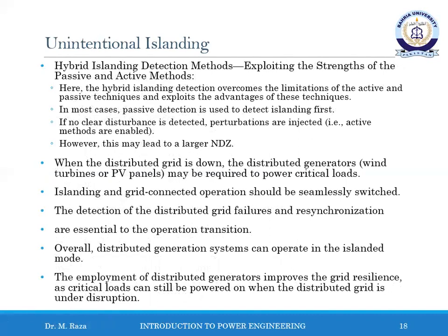Hybrid islanding detection methods use the strengths of the passive and active methods. Here, the hybrid islanding detection overcomes the limitations of the active and passive techniques and exploits the advantages of these techniques. In most cases, passive detection is used to detect islanding first. If no clear disturbance is detected, perturbations are injected, that is, active methods are enabled. However, this may lead to a larger NDZ.